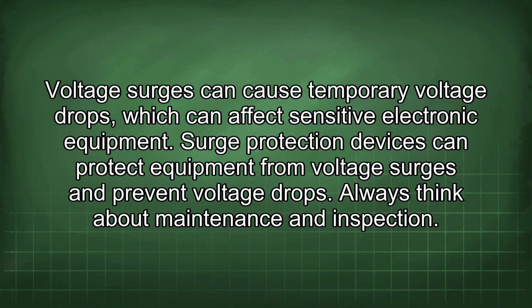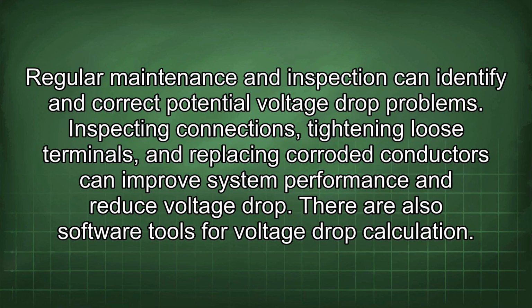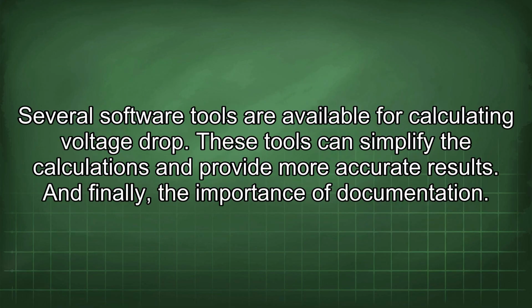Always think about maintenance and inspection. Regular maintenance and inspection can identify and correct potential voltage drop problems. Inspecting connections, tightening loose terminals, and replacing corroded conductors can improve system performance and reduce voltage drop. There are also software tools for voltage drop calculation. Several software tools are available for calculating voltage drop. These tools can simplify the calculations and provide more accurate results.